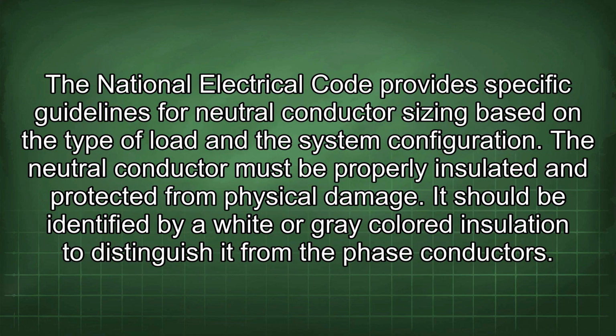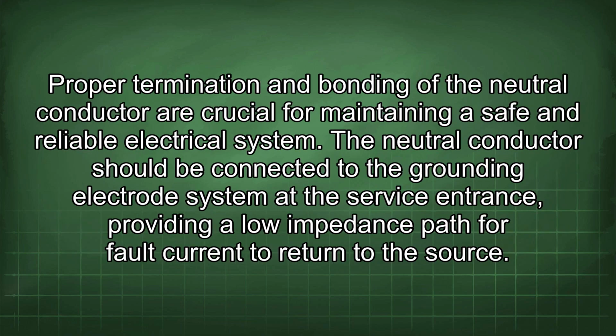The National Electrical Code provides specific guidelines for neutral conductor sizing based on the type of load and the system configuration. The neutral conductor must be properly insulated and protected from physical damage. It should be identified by a white or grey-colored insulation to distinguish it from the phase conductors. Proper termination and bonding of the neutral conductor are crucial for maintaining a safe and reliable electrical system. The neutral conductor should be connected to the grounding electrode system at the service entrance, providing a low impedance path for fault current to return to the source.